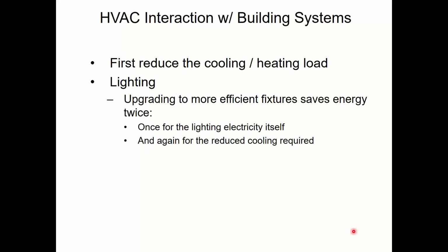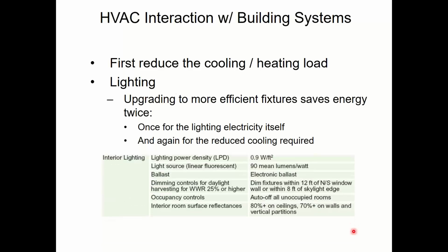So it's going to reduce my cooling load requirement. And it can be quite substantial. Lighting used to be a giant portion of cooling loads when we had, like, 1 watt per square foot of load coming off of that thing. Now with LED lights, it's so minimal. It's a giant savings. And lighting is no longer the largest portion of our cooling needs.